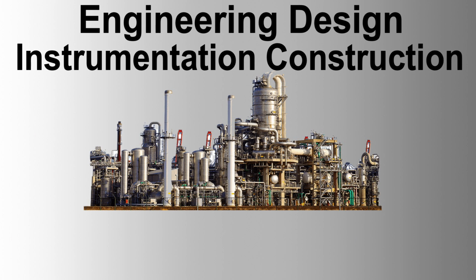Where the contractor considers that the location or the method of installation of any instrument requires clarification, he shall consult with the company for a directive, and whose approval must be obtained prior to starting work on the installation. Instrumentation and equipment shall not be mounted on or from process pipework, vessels, or handrails unless specifically stated in the project drawings, or where prior approval is obtained from the company.